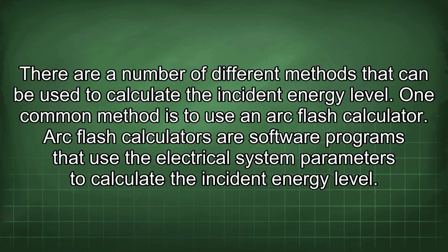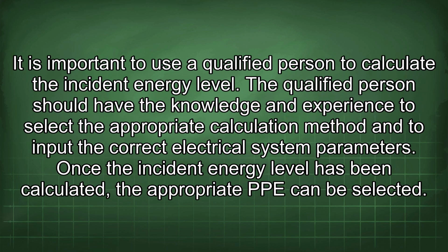There are a number of different methods that can be used to calculate the incident energy level. One common method is to use an arc flash calculator. Arc flash calculators are software programs that use the electrical system parameters to calculate the incident energy level. It is important to use a qualified person to calculate the incident energy level. The qualified person should have the knowledge and experience to select the appropriate calculation method and input the correct electrical system parameters. Once the incident energy level has been calculated, the appropriate PPE can be selected.